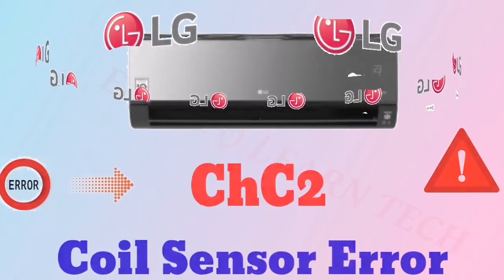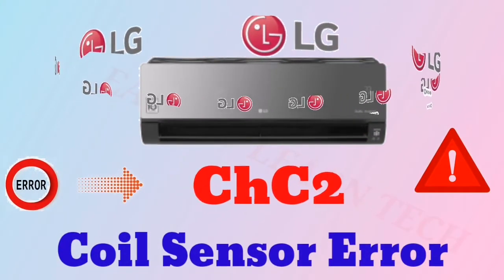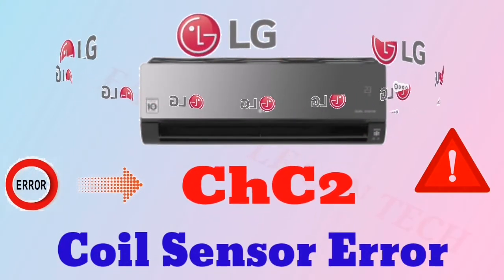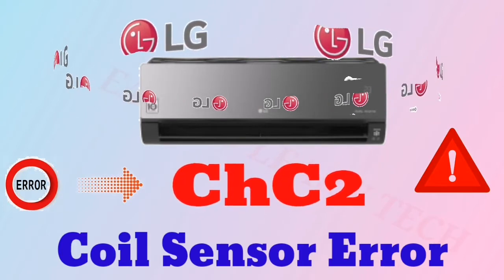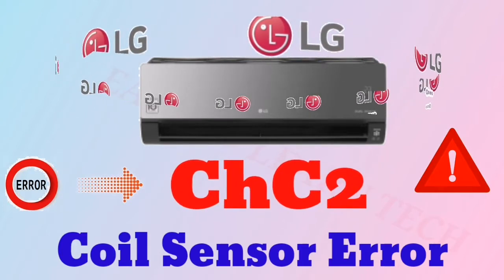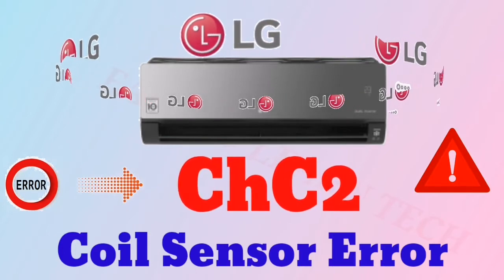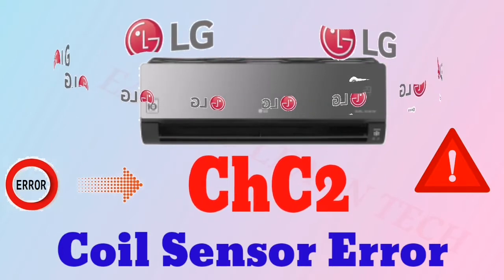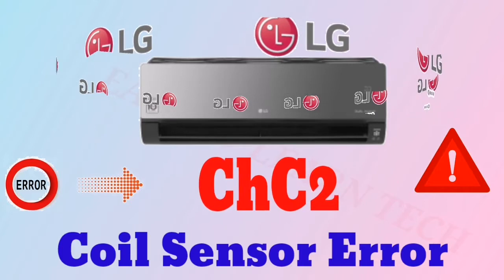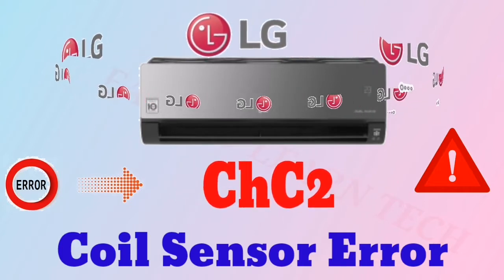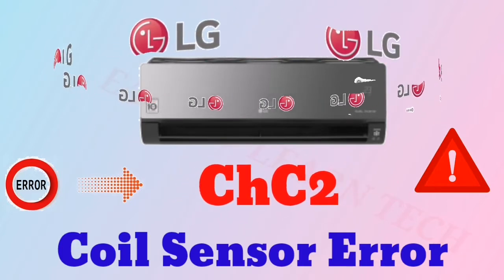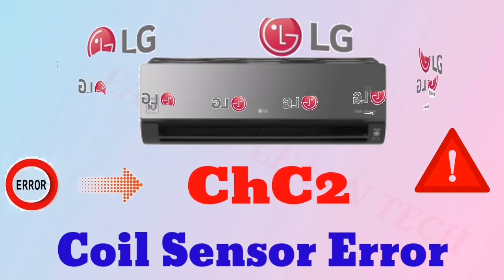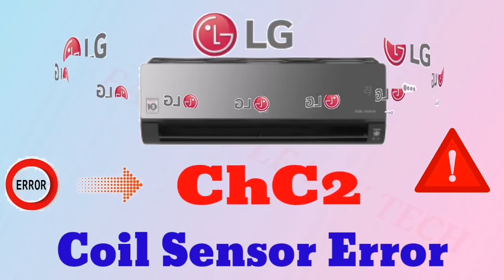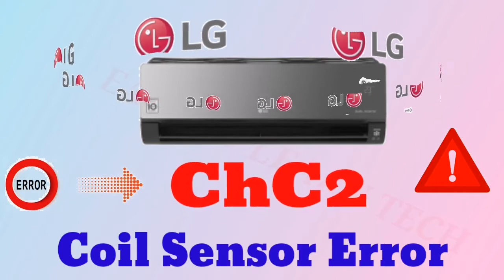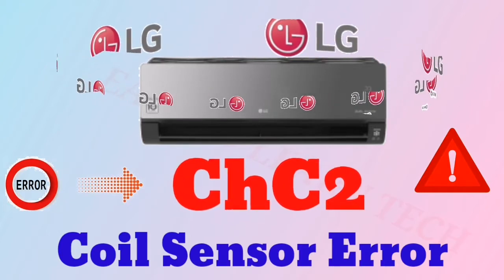Let's see the next error code. When you see ChC2, it means coil sensor error. First of all, you have to check the resistance of your coil sensor, and the resistance should be correct according to the manual. And if the placement of your sensor is not done properly, you have to place it in the right place, because sometimes during maintenance or servicing, the sensor gets displaced from the area. You have to place it in a proper place. And if it is still not working, then you have to check the PCB and change the PCB, and your unit will be in working condition.